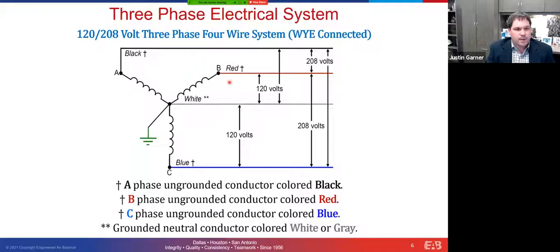And then obviously the voltage potential between any ungrounded conductor and the grounded conductor is going to be 120 volts. You notice here that these are color-coded differently. Most of the time in a commercial facility, you will see black, red, and blue used on the 120/208 side of the power system. And typically your neutral will be white. But again, always double check that because the code doesn't stipulate that they have to use a certain color. It just stipulates that it has to be unique and used uniformly throughout the system.